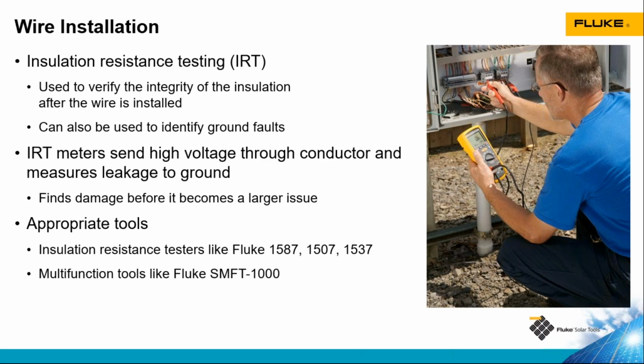Fluke has a series of insulation resistance testers, the 1587, which is shown in the picture on the slide, and the 1507 are handheld insulation resistance testers. They can conduct this test up to 1000 volts. We also have the 1537. This is a relatively new insulation resistance tester. It can test up to 2500 volts in 100-volt increments from 250 to 2500. That's a really excellent tool for testing 1500 volt systems where you need an insulation resistance test above 1000 volts. We also have the SMFT 1000. We'll be talking about that quite a bit.